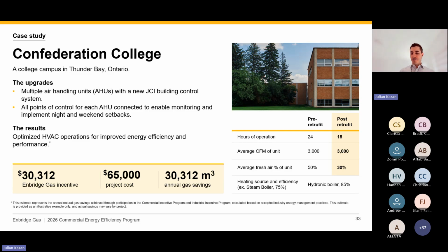So what we did was, we worked with Confederation and we just reduced the hours of operation, right? They shouldn't be running when there's no students even in the classroom. And based on the ASHRAE 62.1 ventilation guidelines, we could determine how much fresh air is actually required for this zone type and the square footage of this space, and tune the units down. So we dropped the hours of operation, we dropped the fresh air, there's gas savings.